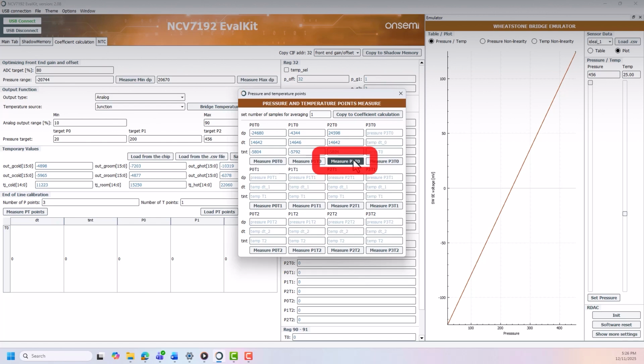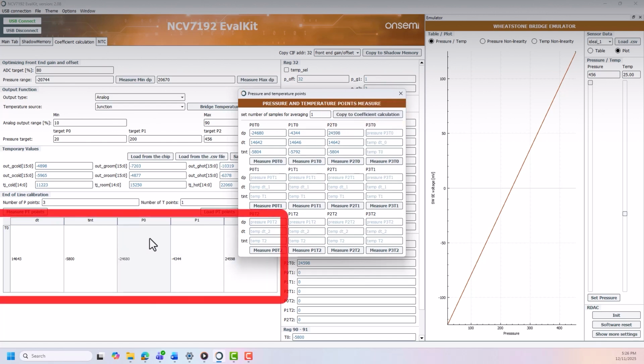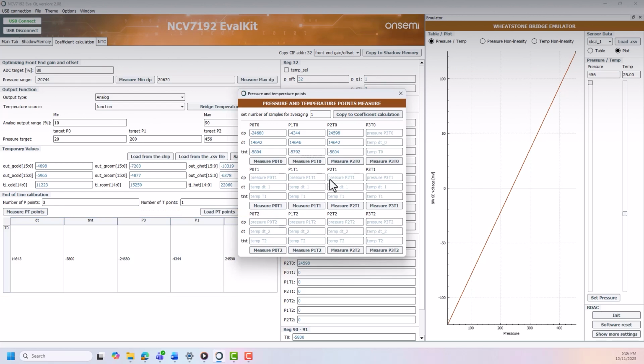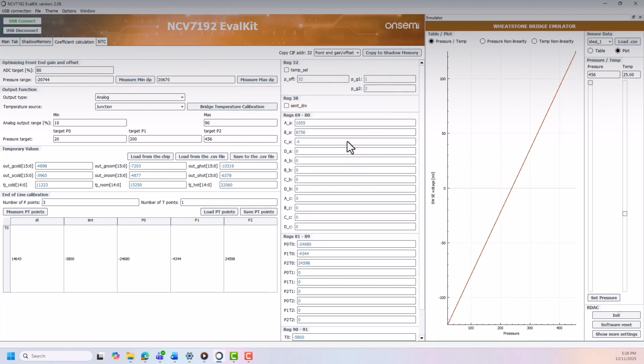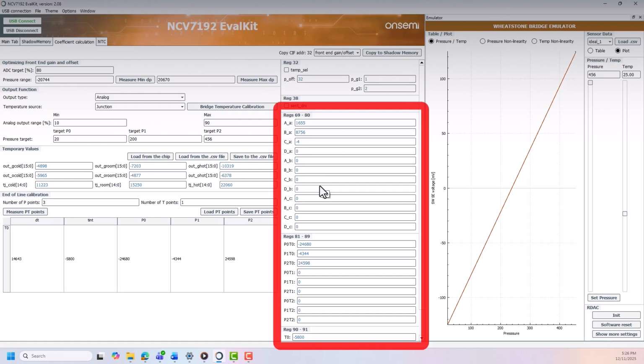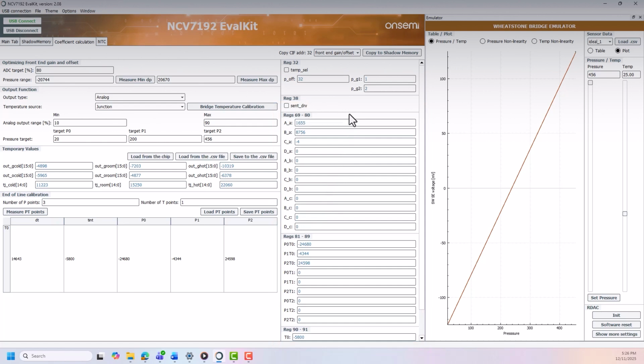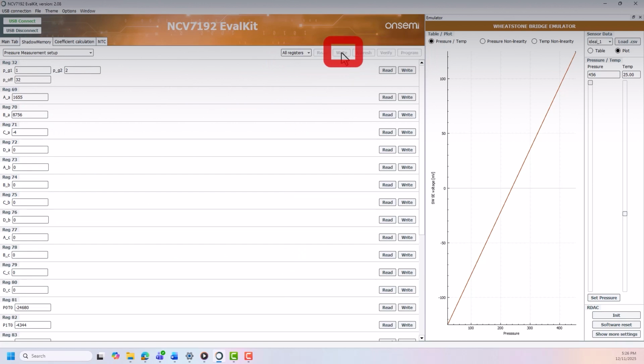Click on the Copy to Coefficient Calculation button. This will copy strobed samples to Table on the Coefficient Calculation tab to the lower table. You can now close Window for strobing the PT points. On the right side here, you can see that the tool automatically calculated coefficients for the DSP. We need now to copy them into device memory. On the right upper side, select Calibration Coefficients from the menu and click on Copy to Shadow Memory button. Now on Shadow Memory tab, click Write button to send the data to the chip. We can also click on Program button to store all coefficients in the EEPROM. This will ensure that the calibration will stay in the device even after leaving calibration mode or reset.